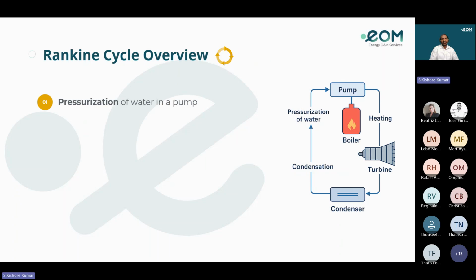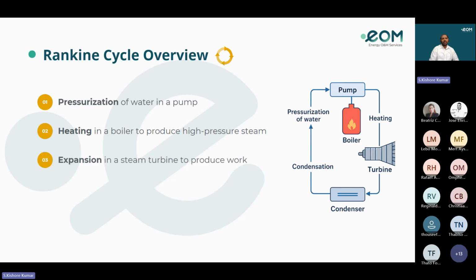Here we can see the Rankine cycle. The Rankine cycle serves as the primary model for analyzing steam turbine performance. It involves pressurization of water in a pump, heating in a boiler to produce high-pressure steam, expansion in a steam turbine to produce work, and condensation in a condenser to return water to the pump. In the image, we can see the pump: the water is pressurized in the pump and goes to the boiler, where it is heated, and the steam goes to the turbine. Once the work is done, it goes to the condenser, which condenses the steam, and it returns back to the pump.